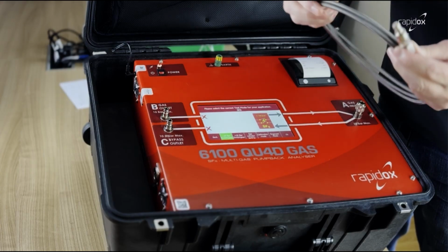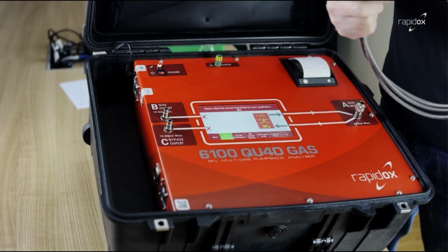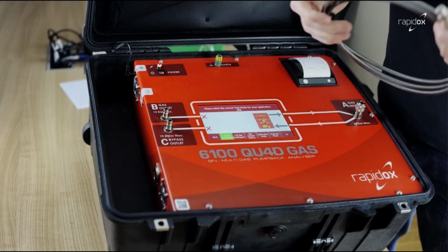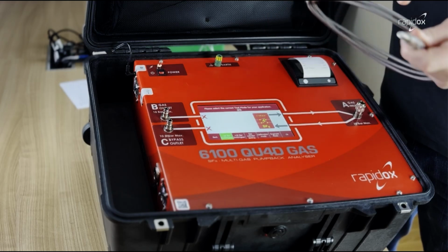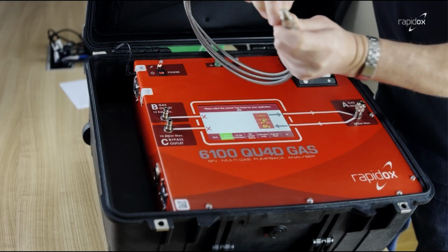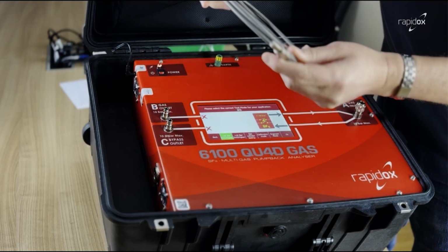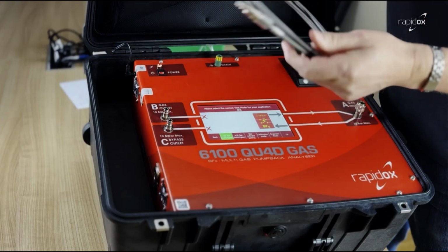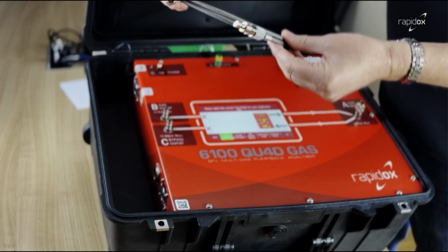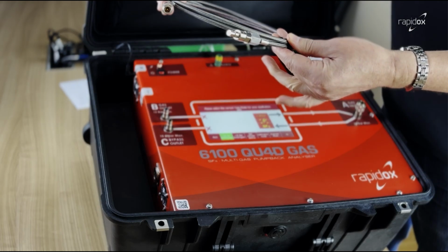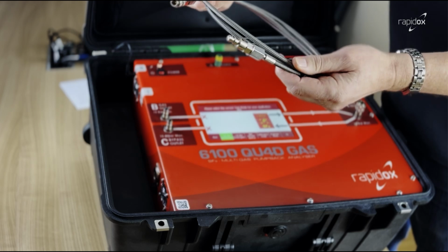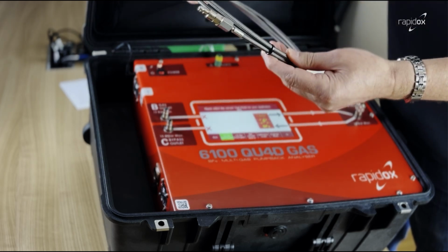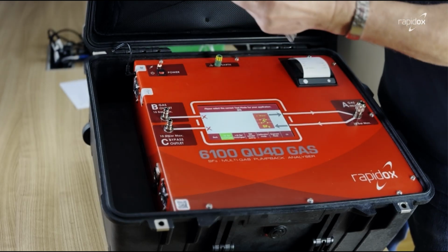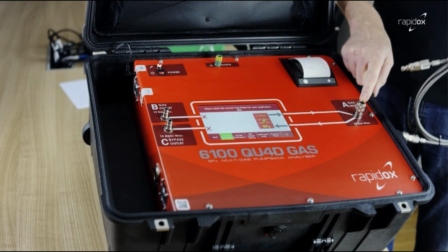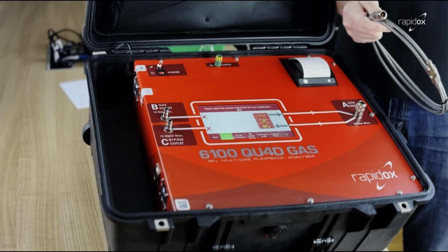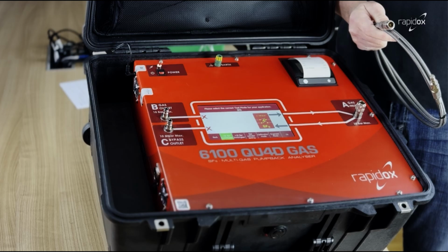The male fitting and the female fitting, you can see here, one's got a pin inside, and the pin seals this so no gas can get inside. And on the male side there's also a closed shutter here, which is also sealed, and this means that the hose is gas tight, and when we supply it, it's actually dried and filled with SF6 or other gases like carbon dioxide, depending on the analyzer. And we do this to make sure the hose is supplied to you dry and ready to use. So the male fitting fits into the female fitting over here, and then the female fitting will attach to the measurement point on the electrical apparatus.